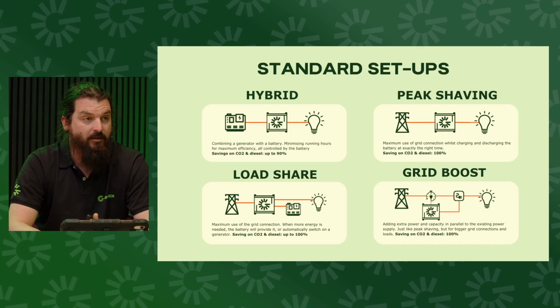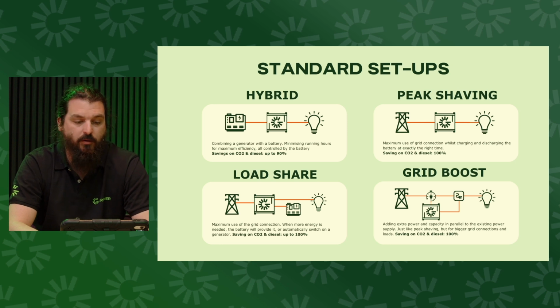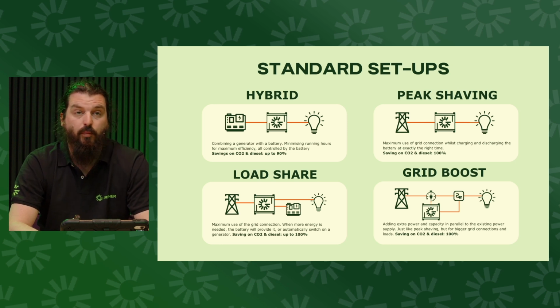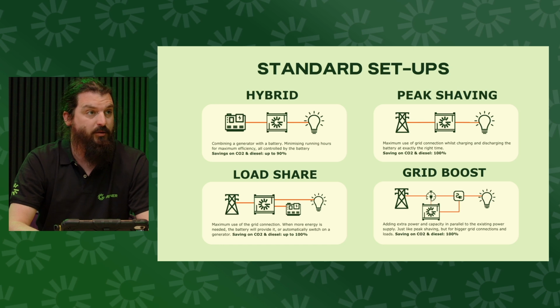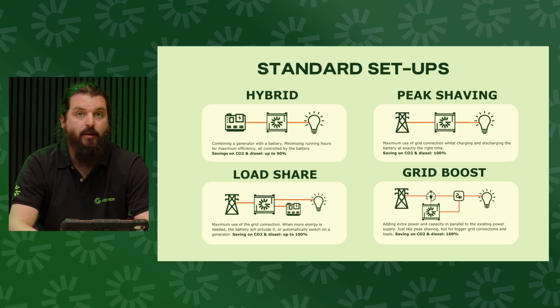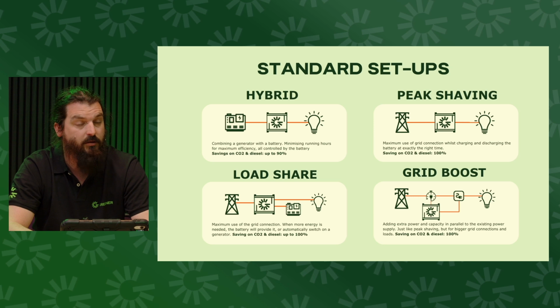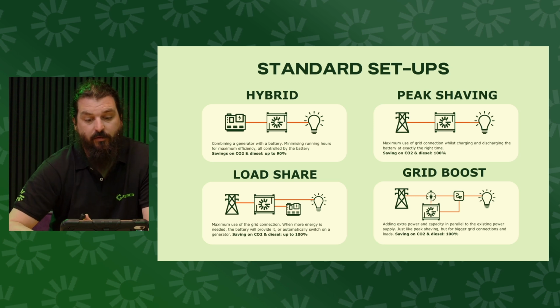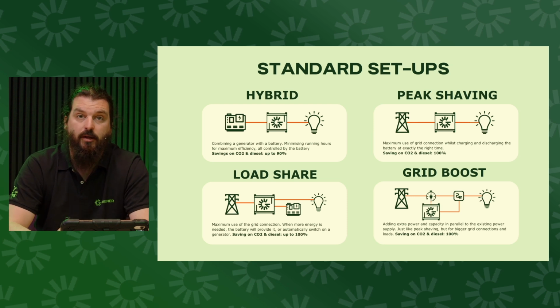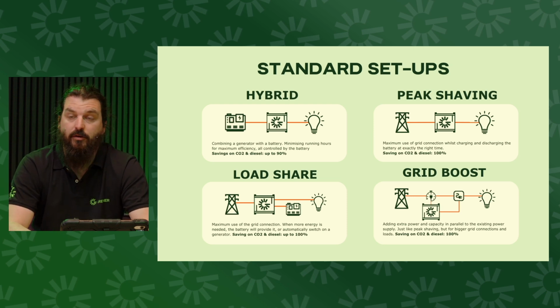The difference is mainly where the energy is actually coming from. In a hybrid system, we use a switchable power source, which needs to be at a specific load in order to be efficient—could be a generator, could be a hydrogen cell, could be anything else. Our peak shaving setup is when we have a constant power supply and we wish to keep the battery as full as possible, then add energy from the battery when required.